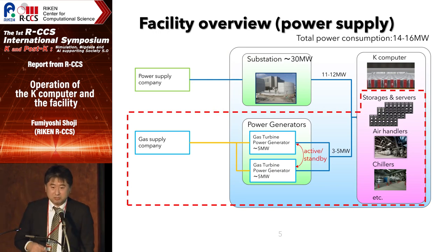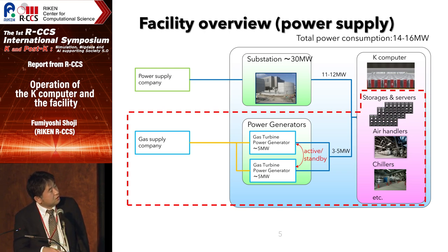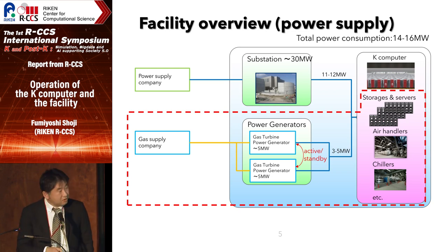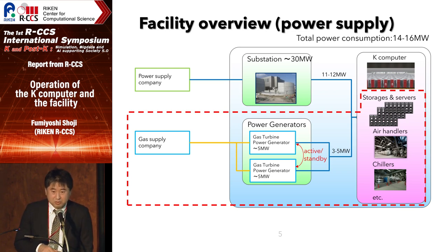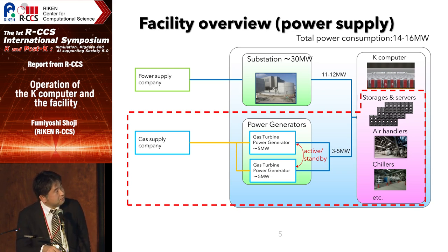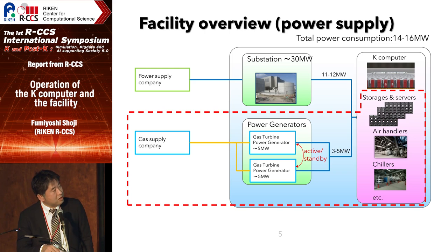I will now show you the facility of this site. We have two power paths to the power supply company. About two-thirds of the total power consumption comes from the power supplier, and one-third is generated by our own gas power generators. These power generators can generate electricity up to five megawatts, and they also work as backup power sources for the storage systems, but not for the K-Computer itself.